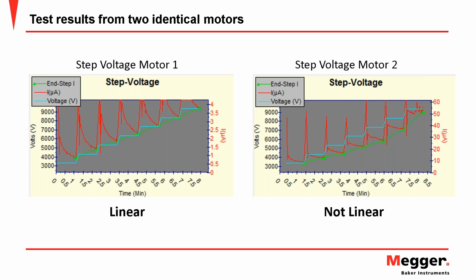Now, as we move into high pot, and specifically we recommend step voltage testing because there's just so much valuable information that comes out of step voltage testing in the form of this linear response curve. And here's a great example of two identical motors. These are 4,000 volt motors. We do this incremental stepping of the voltage. The cyan color there is the voltage level, and the red represents the charging current and then subsequent leakage current at each of these steps. And we see this asymptotic decay, which is normal.